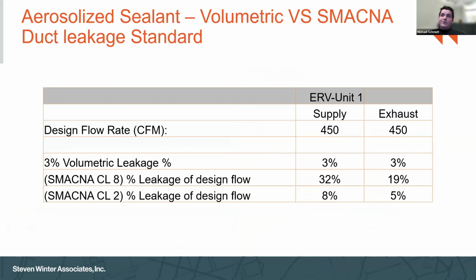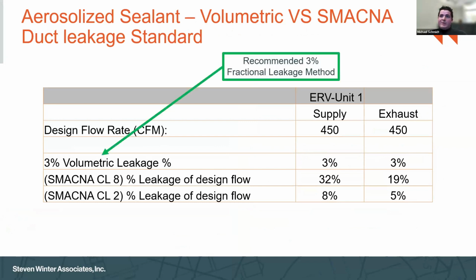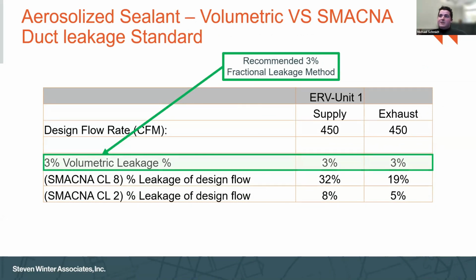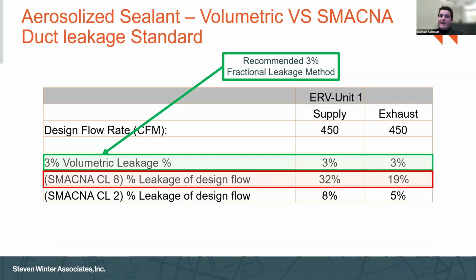All right, and this chart will demonstrate, on a real project example, the differences that you can come across using that volumetric or 3% approach versus the SMACNA duct leakage approach. Of course, we're recommending 3%. Why is that? For this particular case, this ERV unit, we have 3% across the board, right? Supply and exhaust air streams are both sealed down to 3% duct leakage. As the project was originally specified by the engineer, it was done under the SMACNA duct leakage standard, and here we can see that we're allowing essentially 32% duct leakage using aerosolized sealant. And I just told you we can get that down below 1% duct leakage, right? So 32% is pretty egregious for a new high performance building, right? We shouldn't be allowing 30% duct leakage in a high performance project, and I think that's just inadequate for all of our efforts in decarbonization and building better, right?